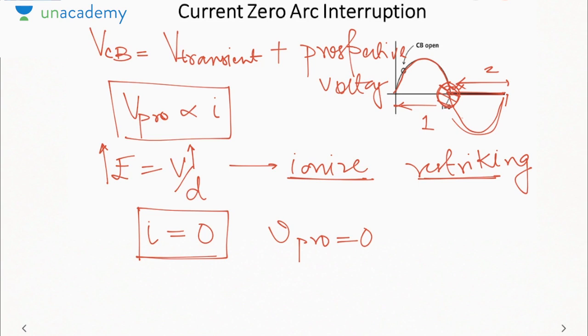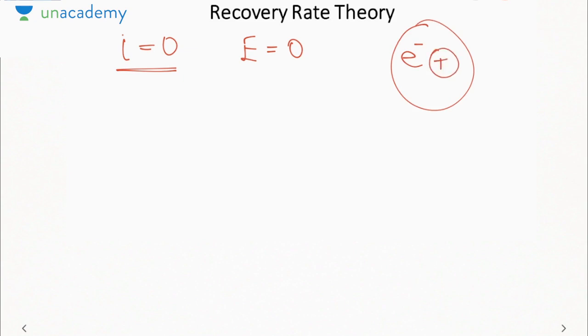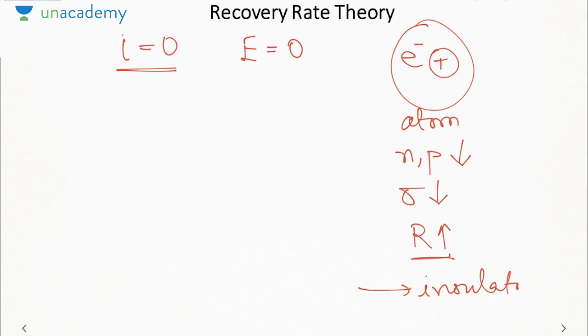This depends on theories called arc interruption theories. The first is the recovery rate theory. When current becomes 0, the electric field also becomes 0. If electric field is 0, electrons and ions are not displaced in opposite directions; rather, they start to recombine. If electrons and ions recombine, they form atoms, and the number of charge carriers, N and P, reduces, due to which conductivity reduces and arc resistance increases. As arc resistance increases, it starts becoming an insulator again, so we say air starts regaining its dielectric strength.